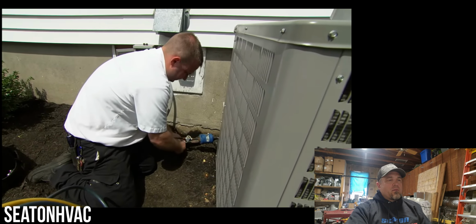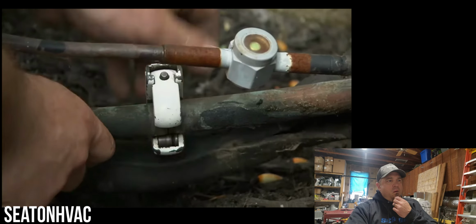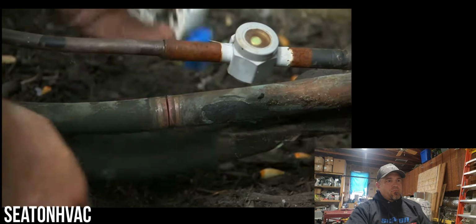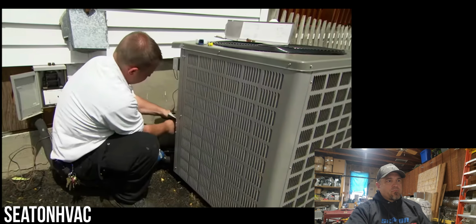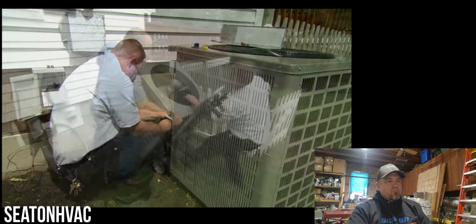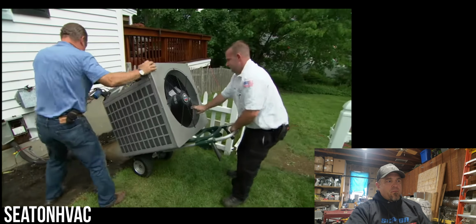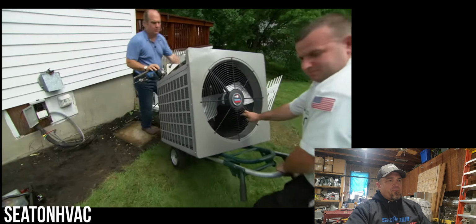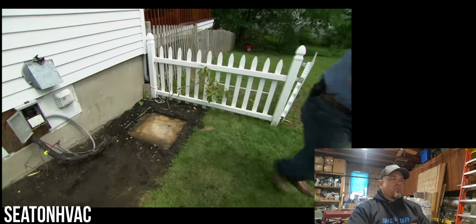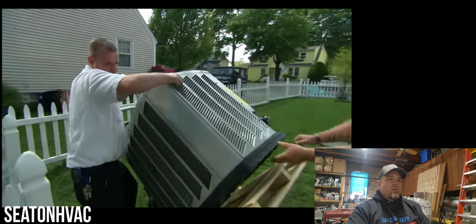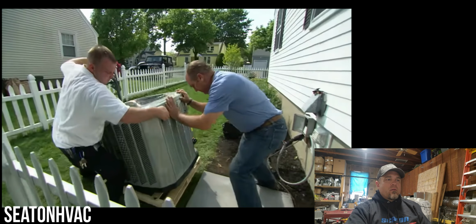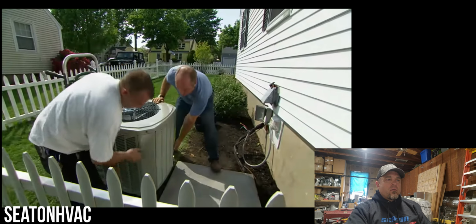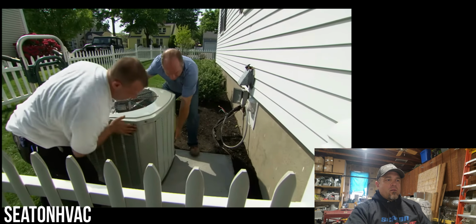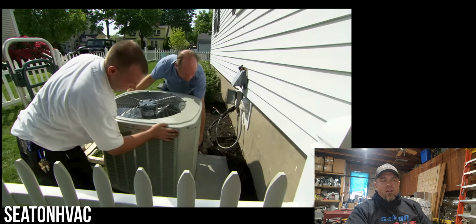With all the refrigerant gone, we can now remove the old unit. Keith will cut the copper line sets, disconnect the electrical, and remove the old unit. Here's our new 3-ton condenser. All right, let's just slide this on. So it looks like they went with a 3-ton.